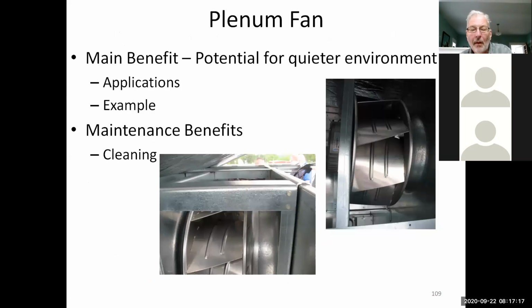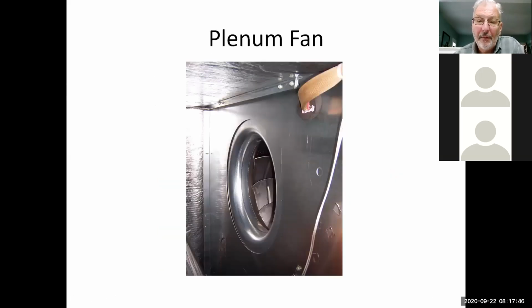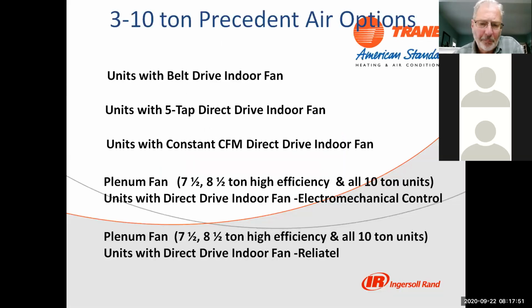Now, the other thing to remember on these is you cannot make them turn backwards. So even though these are on 3-phase units, you cannot make them turn backwards. They're auto-correcting. So don't use them to determine whether or not you've got the proper polarity on a rooftop. Use the compressor. We'll get into that a little bit too. But if you change the polarity on a 3-phase rooftop, it's still going to turn the same direction. These fans don't change direction. And this just shows the side of the fan where it draws the air in.